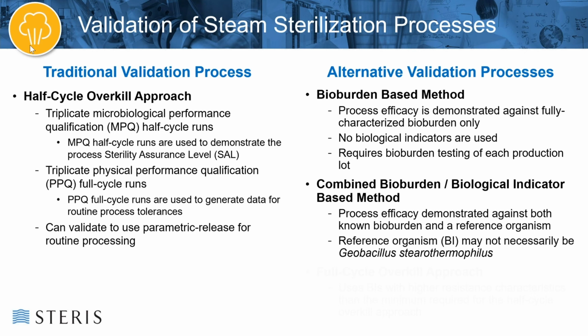But when you're using the combined bioburden BI method, you might not necessarily use Geobacillus stearothermophilus. You could use, for instance, Bacillus subtilis with a known D value that is much less than Geobacillus stearothermophilus. And quite often I'm dealing with products that the customer or the product themselves need to be processed at lower temperatures below 121 degrees C.